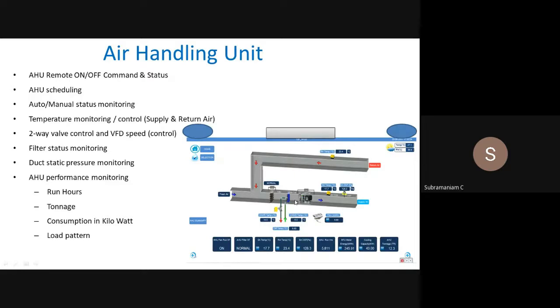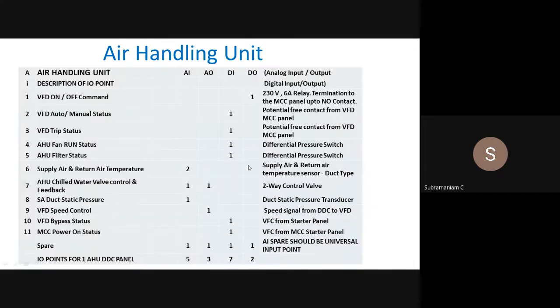And for control, there are some things which are used based on the set point. If I want to control this AHU based on return air or supply air or some other logic: if it is an operation theater, there is a separate logic. If it is a normal or a pharma application, it may be a different logic. So we have to understand the design intent by the HVAC designer, and then accordingly build these IO points. Now this is a typical IO point list, how you construct it.